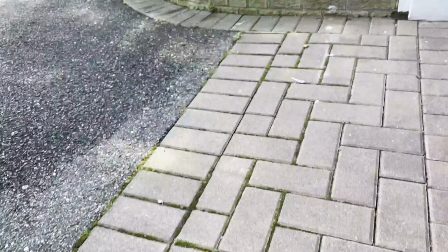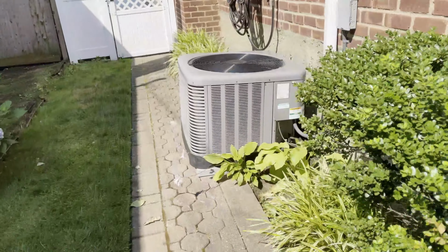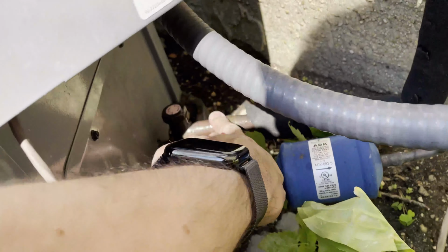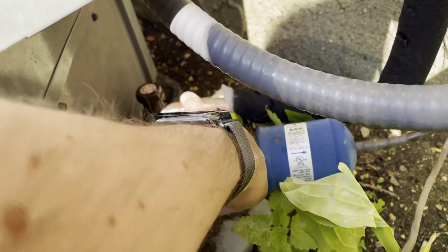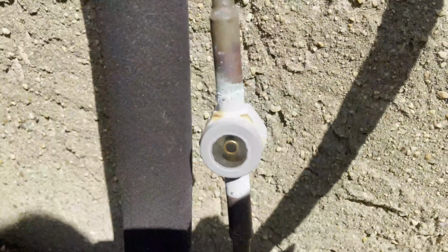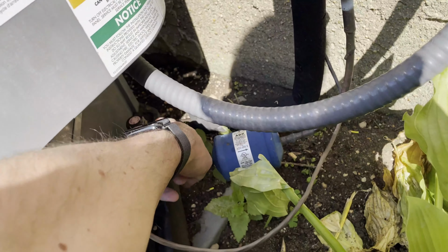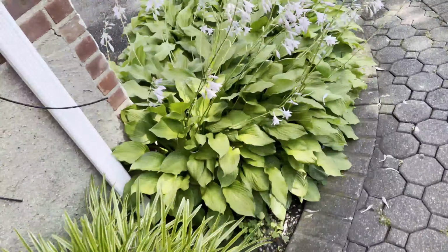So we're gonna run outside and see if I catch it before it comes back on. Dang it. Do you hear that? I just heard it. It just ticked back on. But I bet I can, yes, this suction line is barely cold at all. So it was off. See the bubbling in there as it's starting back up again? It just started up. Unfortunately, I was not able to catch it while it was off.